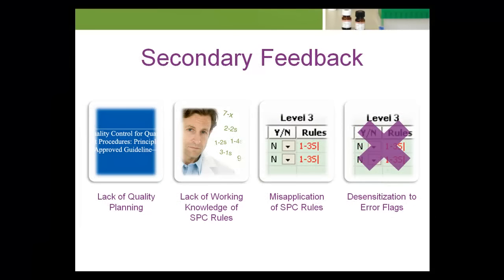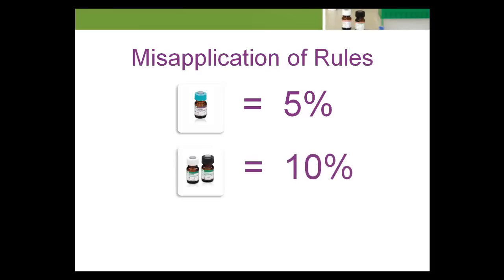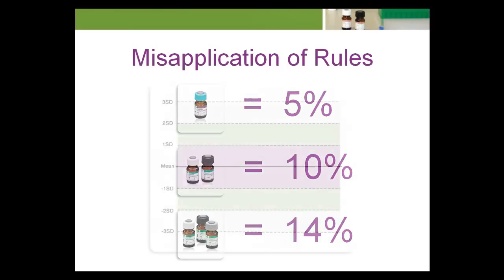Regardless of the analytical capabilities of a test, some laboratories will continue to use only a 1-2-S rule as a rejection limit. According to Dr. Westgard, failure to allow for valid points between 2-SD and 3-SD may result in falsely rejecting 5% of analytical runs when using one level of control, 10% of analytical runs when using two levels of control, and 14% of analytical runs when using three levels of control.